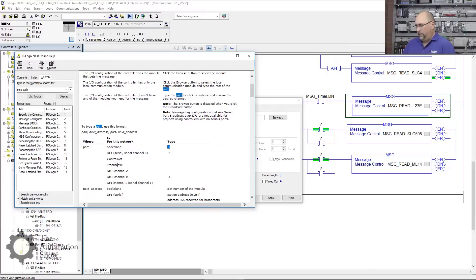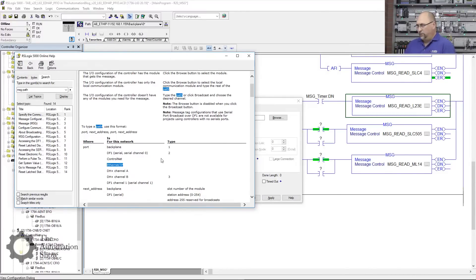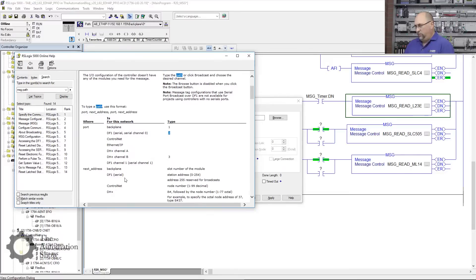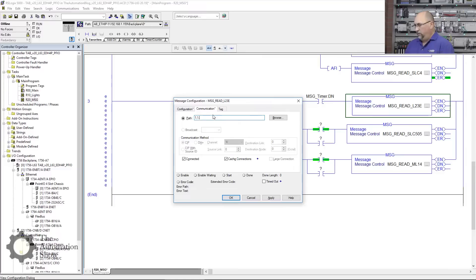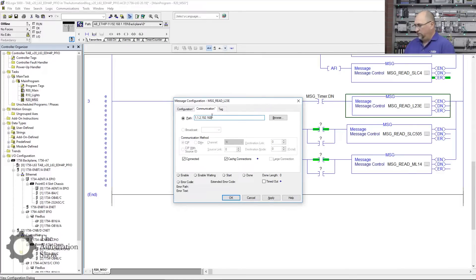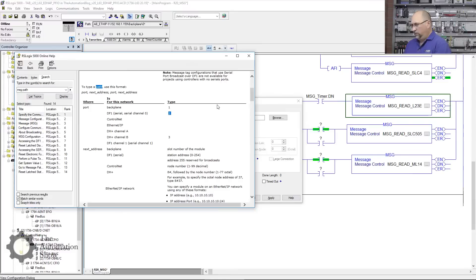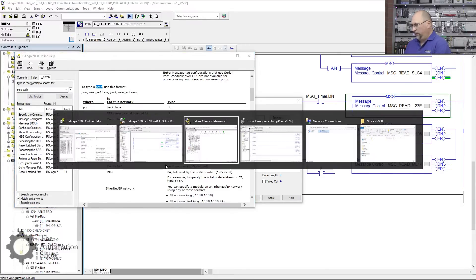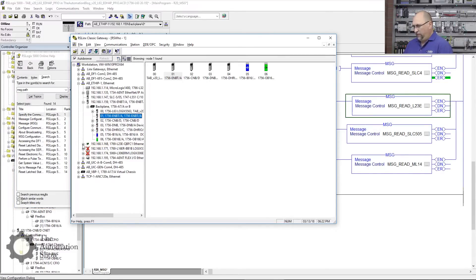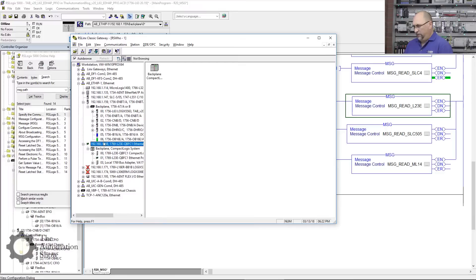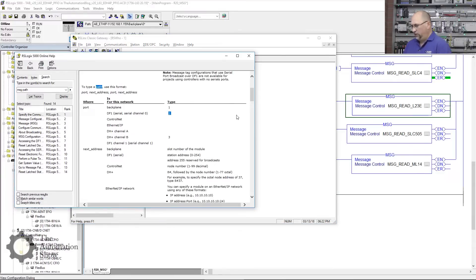What's next? The next thing will be I want to go out the Ethernet IP port on that module, so that's going to be type 2. And the next thing will be the Ethernet IP address. So we'll do 2, comma, then I said it was 192.168.1.168. Let's double-check that. Yep, there she is.